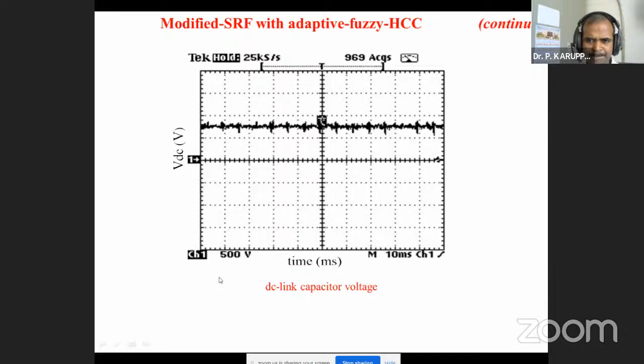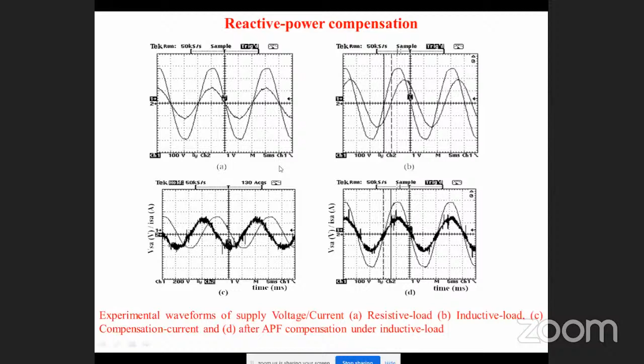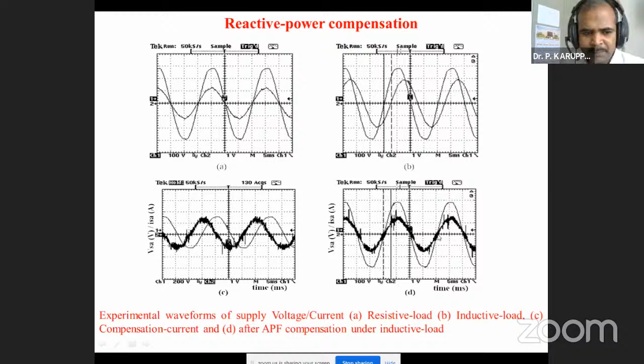This is the reactive power compensation. We took results without the active power filter and with the active power filter. This shows supply voltage versus resistive and inductive load. With resistive load there's no problem, both are in phase. But when we connect an inductive load, there is a phase shift, which needs compensation current. When I applied the compensation current, after active power filter compensation under inductive load, we get it in phase again.